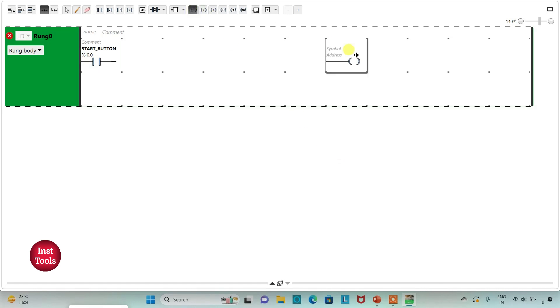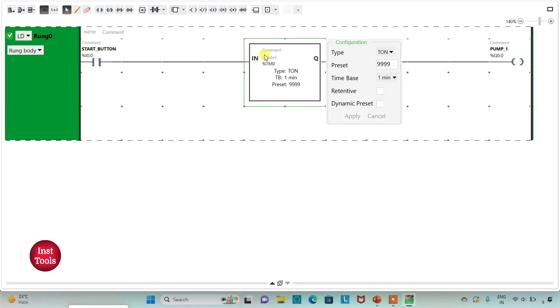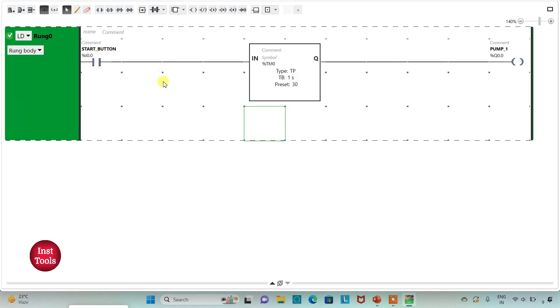I will add a symbol to it as 'Pump 1' — the pump which will fill the tank. The pump should fill the tank in 30 seconds, so the pump should turn on for 30 seconds only. For that I will use a timer for Pump 1, and that should be TP. I will change the time base to 1 second and preset value to 30, then click Apply. When the start button is turned on, the pump runs for 30 seconds, fills the tank, and then turns off.